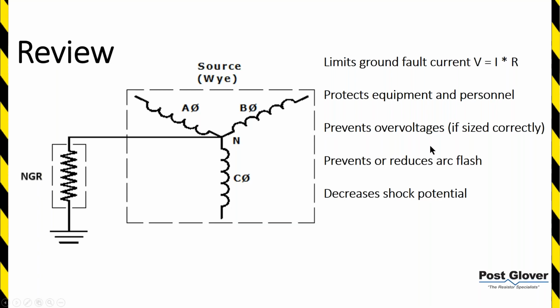It does prevent overvoltages if sized correctly. We're talking about typically intermittent faults in, for example, an ungrounded system. You might have an overvoltage event based on the system's capacitance. We'll talk about that later. But you should prevent those types of events if you are sized correctly on a resistance ground system.